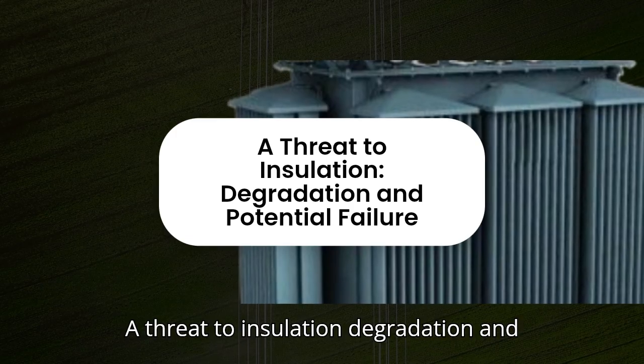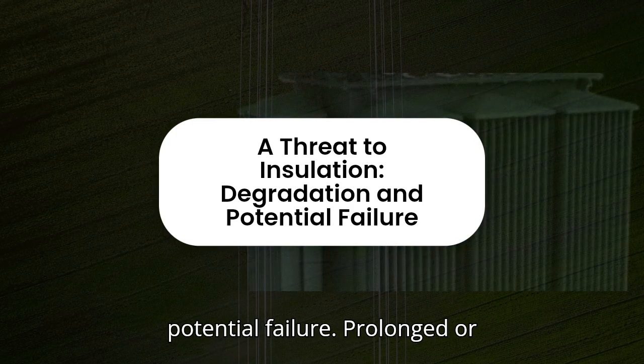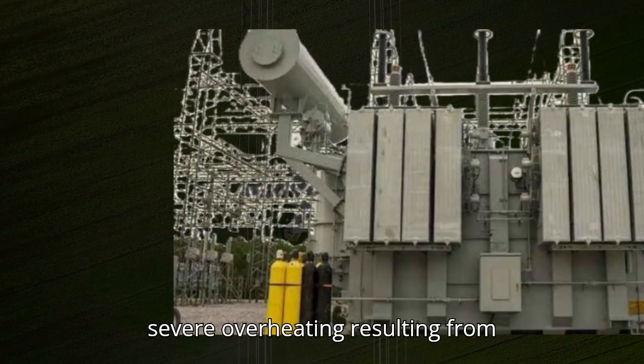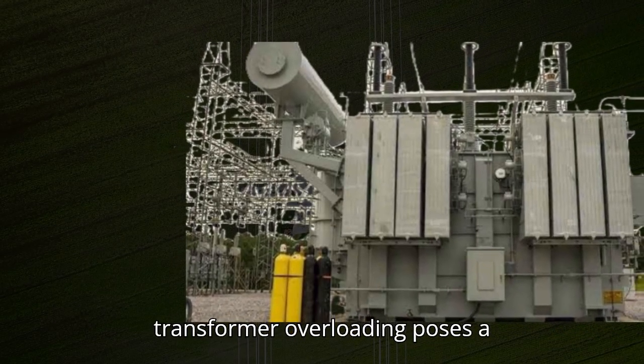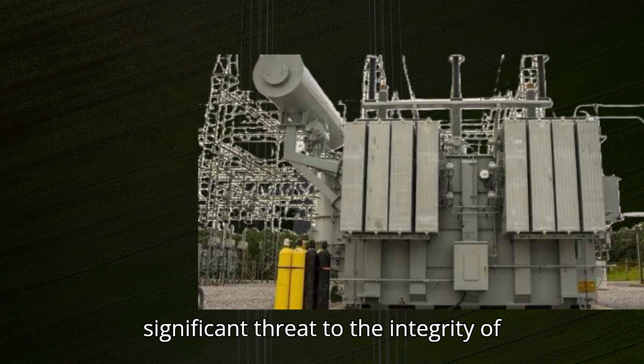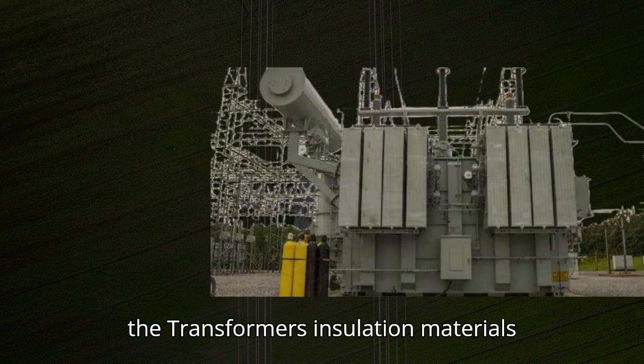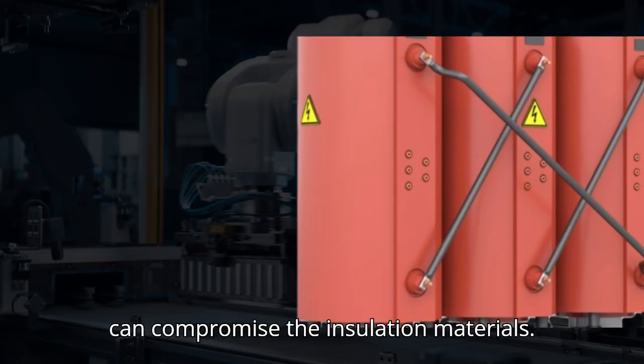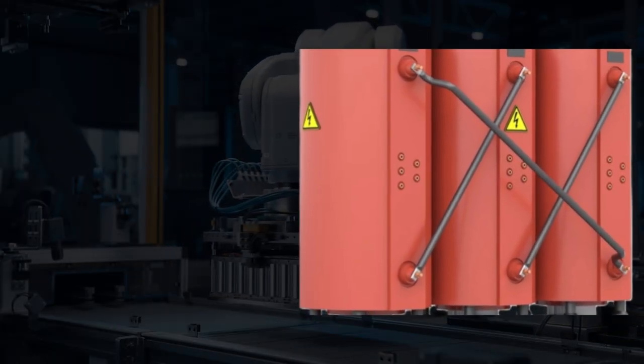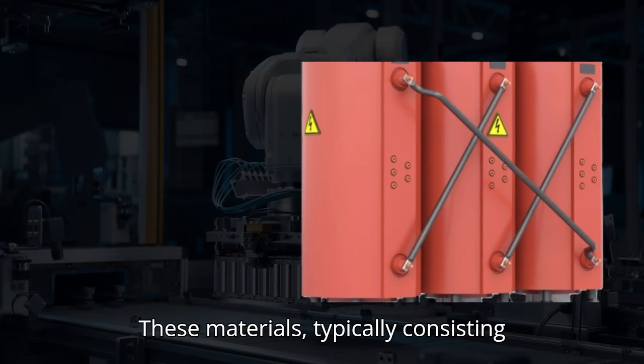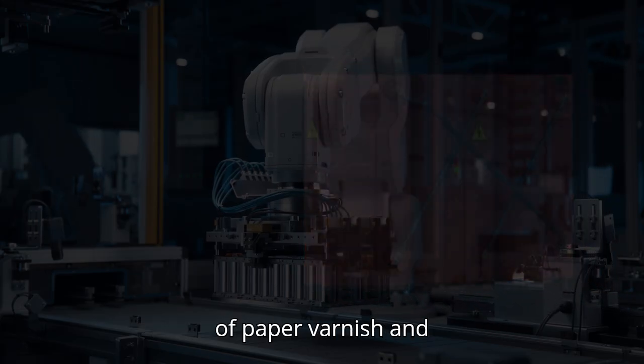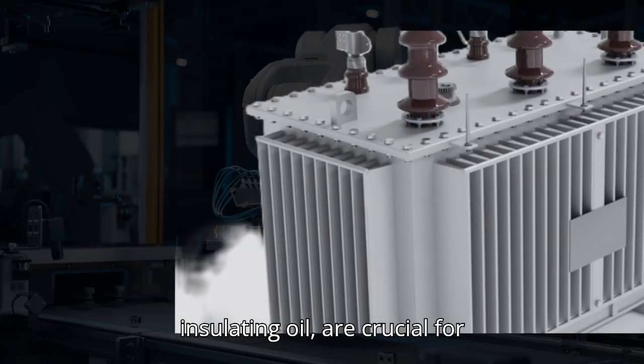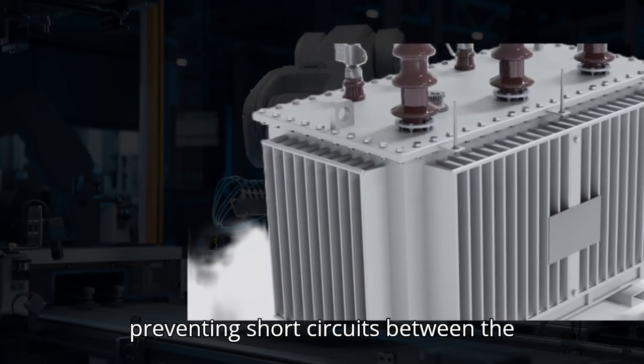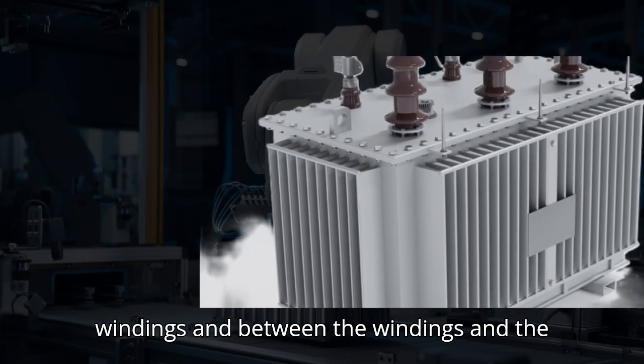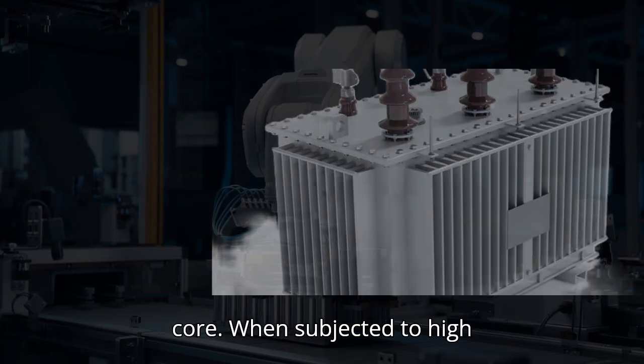A threat to insulation, degradation and potential failure. Prolonged or severe overheating resulting from transformer overloading poses a significant threat to the integrity of the transformer's insulation materials. High temperatures can compromise the insulation materials. These materials, typically consisting of paper, varnish, and insulating oil, are crucial for preventing short circuits between the windings and between the windings and the core.